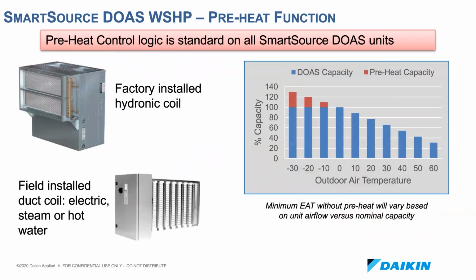And then in some locations, there's a need to design for winter temperatures below the capacity of the unit. In this case, the entering air must be preheated to a point where the DOAS unit can achieve the desired discharge air temperatures. So logic for preheat control is standard on all of our Smart Source DOAS units. If the unit reaches maximum capacity and cannot maintain the discharge air set point, a 0 to 10 volt output signal is modulated until the discharge air temperature set point is met. This signal can control a modulating valve like one of the accessory valves offered for use with our factory installed hydronic preheat coil, or you could use it to control an SCR controlled field installed electric duct heater.